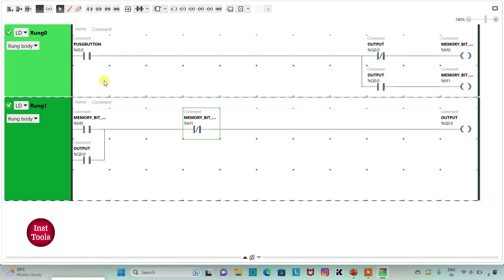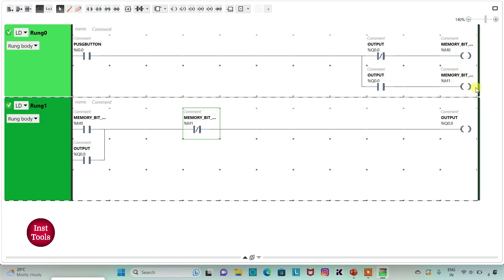So when the push button is pressed and then released — that is when it is turned on — the memory bit which will turn on the output will be true. And then when the memory bit is true, the output will also be true. As I have latched it here, it will remain true when the switch is turned off. And then again when the push button is once again pressed and released, the memory bit which will be used to turn off the output will be activated, breaking the circuit and turning the output off.